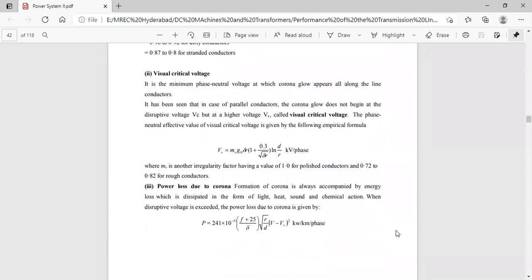The second is the visual critical voltage. It is the minimum phase neutral voltage at which corona glow appears all along the line conductors. This voltage is called the visual critical voltage. It has been seen that in the case of parallel conductors, the corona glow does not begin at the disruptive voltage Vc, but at a higher voltage Vv, called the visual critical voltage. The phase neutral effective value of visual critical voltage is given by the following empirical formula. Vv is equal to mv into g naught into delta into r into 1 plus 0.3 divided by root of delta r into ln of d by r kilovolt per phase, where mv is another irregularity factor having a value of 1 for polished conductors and 0.72 to 0.82 for rough conductors.